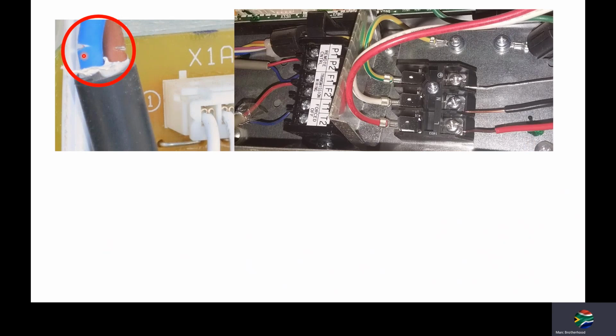Let's look at some poor electrical installations. There you can see somebody has removed the protection and obviously used a blade, but at the same time they've cut directly through the insulation of the 230 volts. Here you can see this is poor installation practice, having well over a centimeter of uninsulated cable. This is single phase, so you're around 230 volt potential.